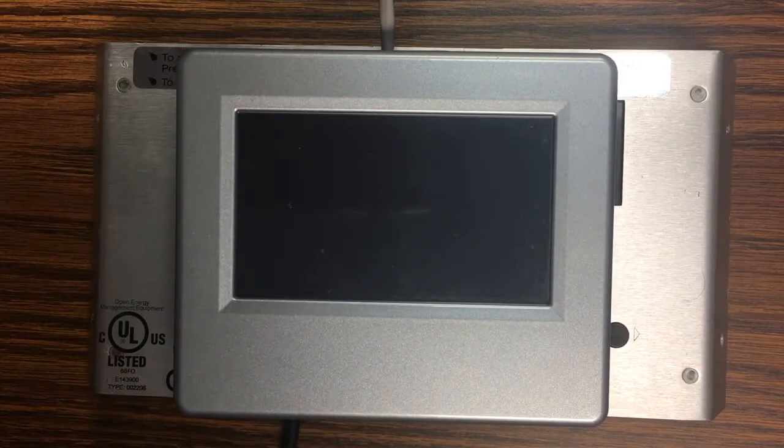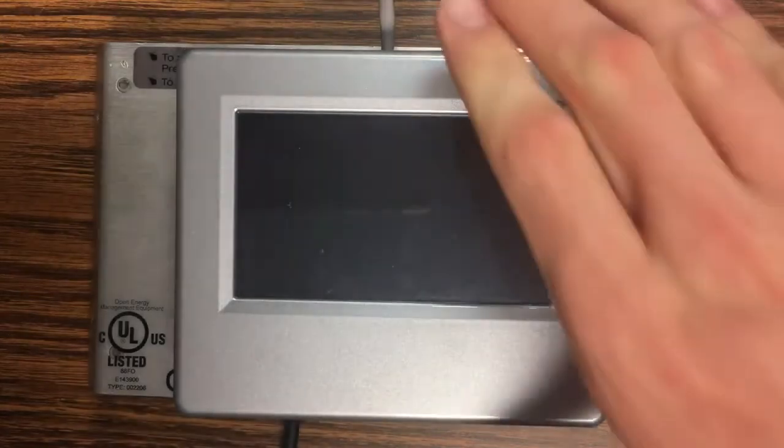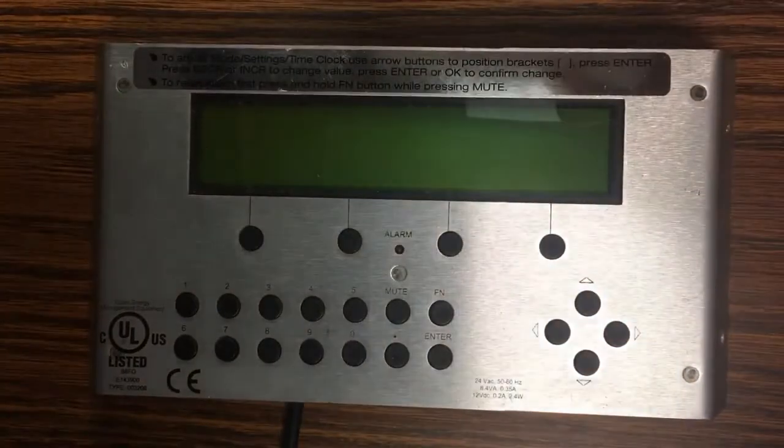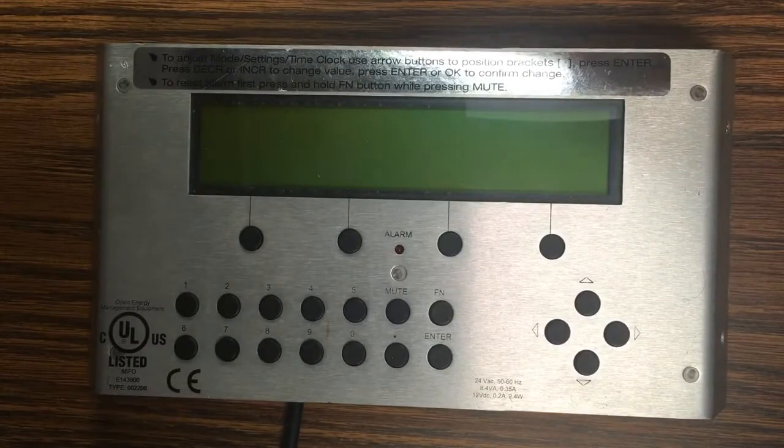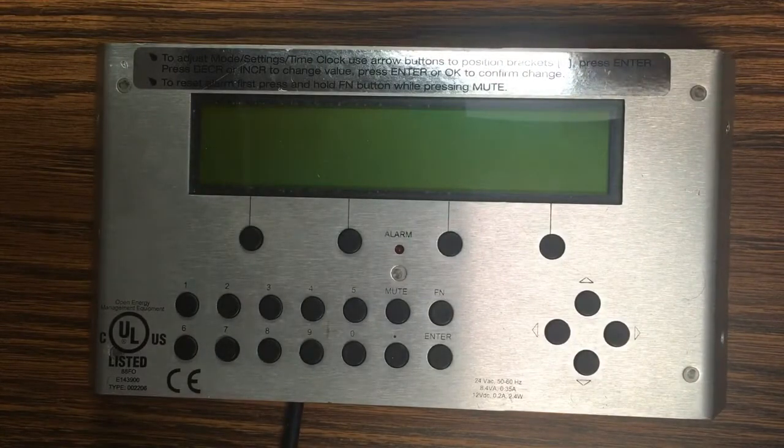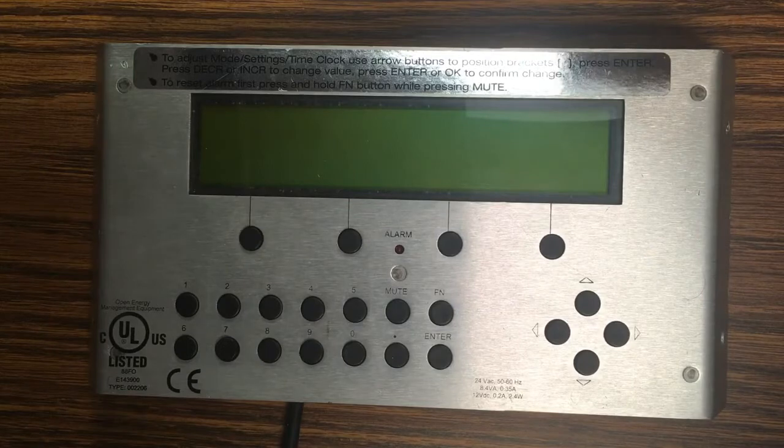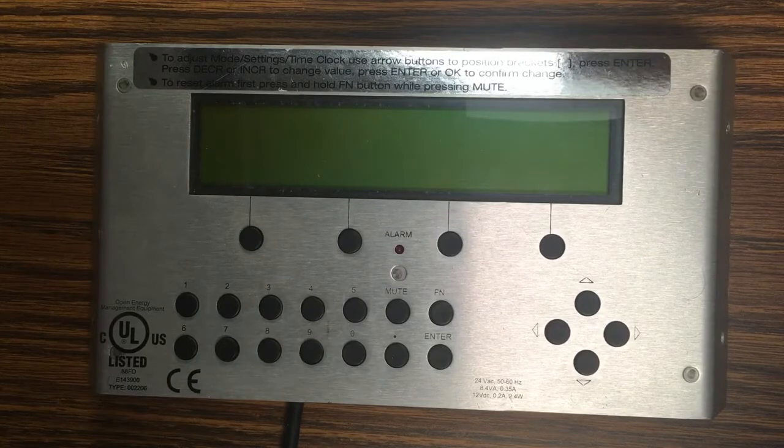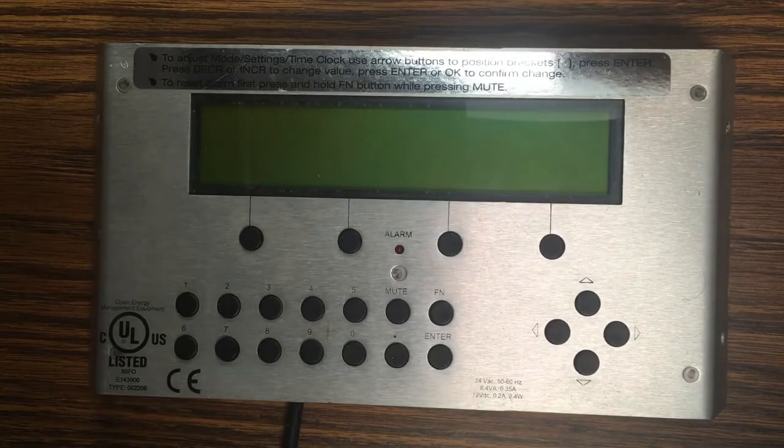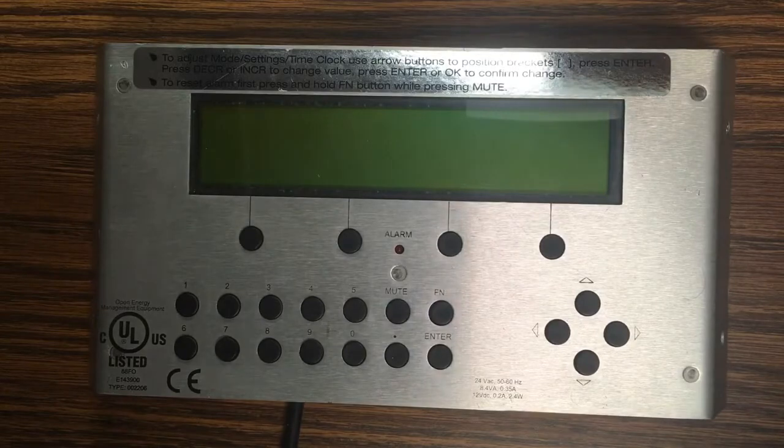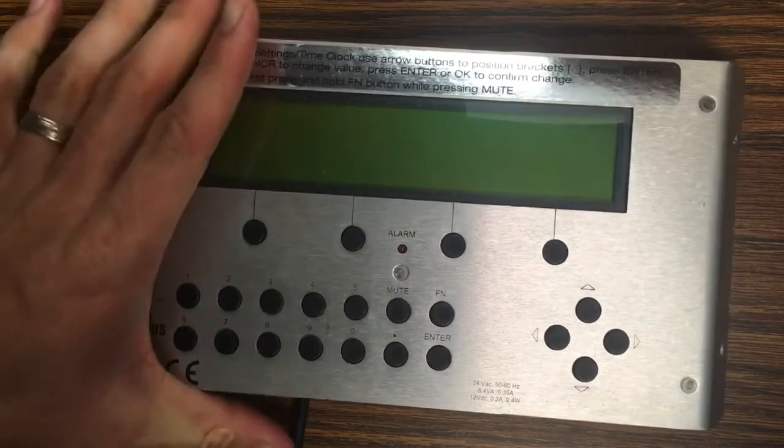You can't simply take a new touchscreen and plug it into a unit that currently has a keypad because the graphics are kept on the controller and a controller can only have one type of graphic on it. So you actually have to reprogram your controller to be able to support a touchscreen. Our service department will be happy to help you with that.